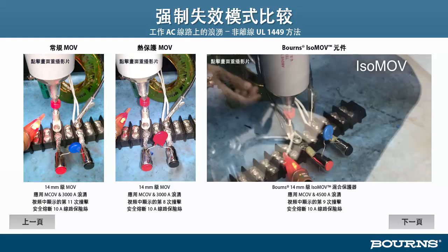The reason it fails so cleanly and so quickly is that after the 8th hit, we were left with an MOV that was just on its last legs. It really was in bad shape, but the gas tube was preventing it from leaking. Had we tested the device, it would have tested just fine. However, on that 9th hit, when the MOV can no longer hold back the GDT's follow-on current, it blows the fuse so quickly that there's no energy release to cause a lot of problems. I hope that was fun for you.